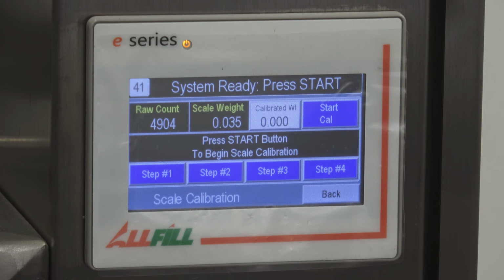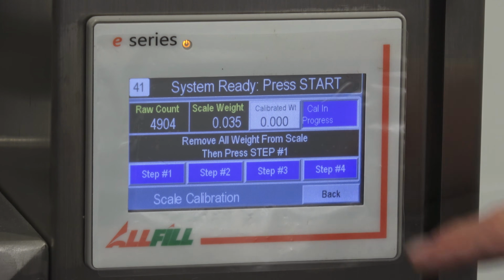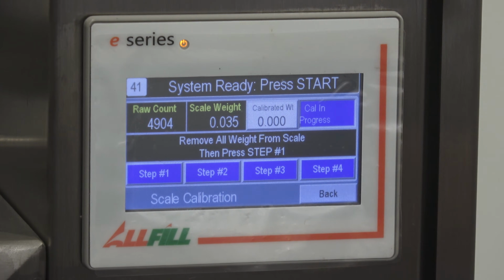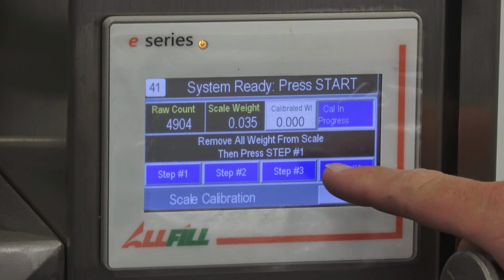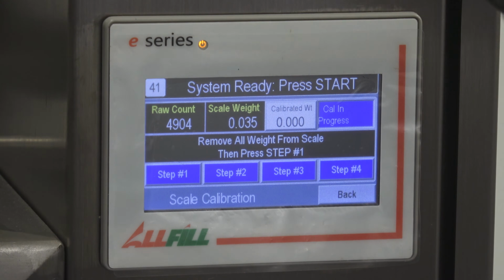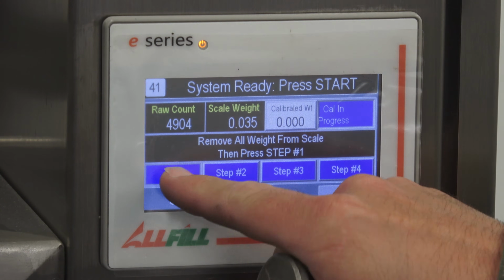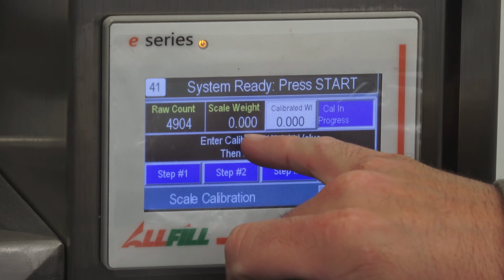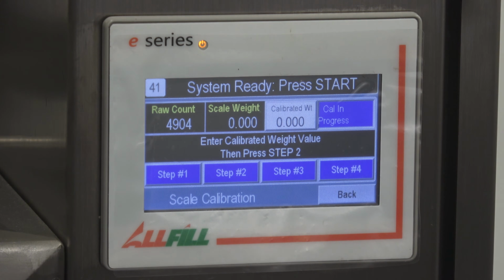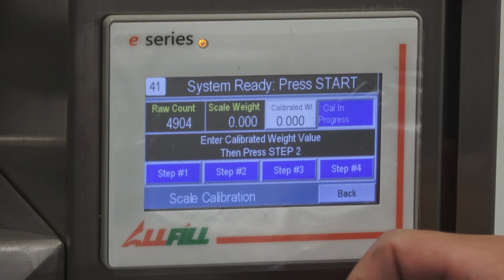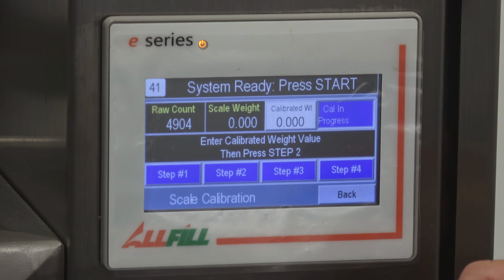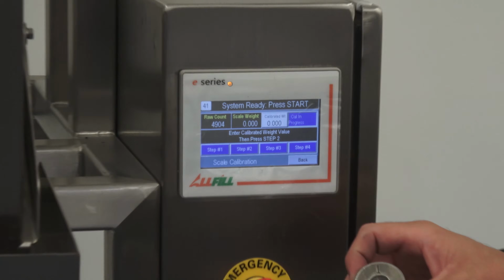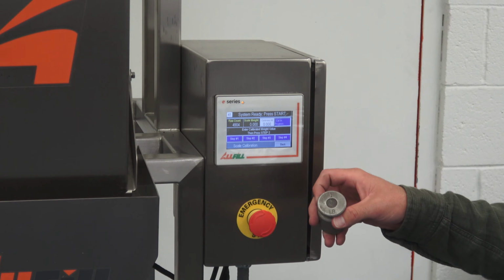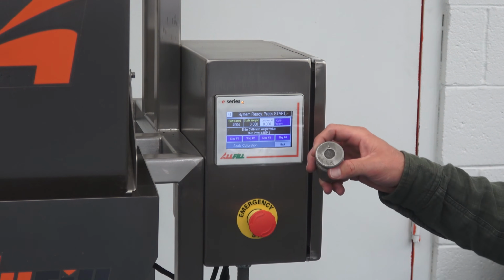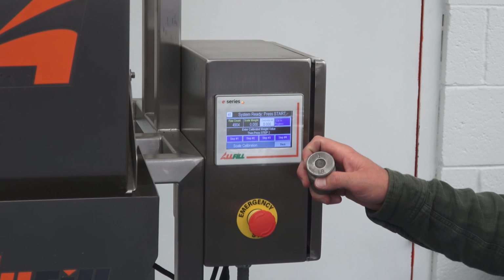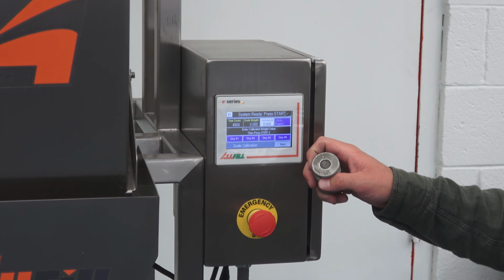The first thing we're going to do is hit start calibration. It says calibration in progress. Remove all weight from the scale, then press step 1. We have no weight in the scale, so I'm going to hit step 1. You'll notice it just cleared the tare weight of the scale. Now step 2 is enter the calibration weight value. This is where we can decide if we want to do it in pounds, ounces, or grams by what we put in. So it's 1 pound, 16 ounces, or 454 grams.